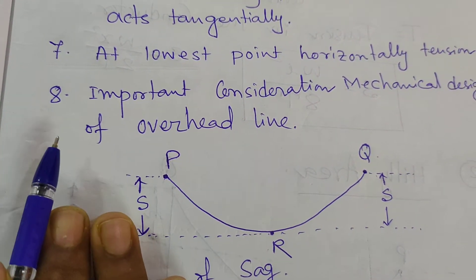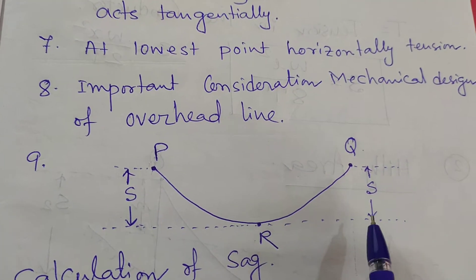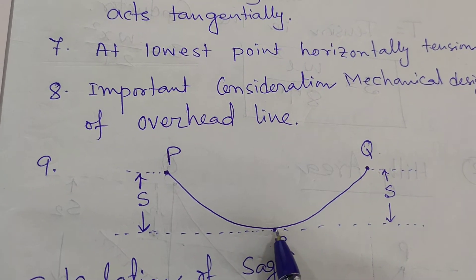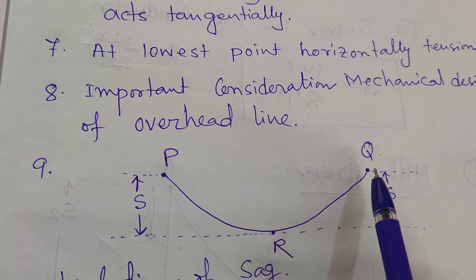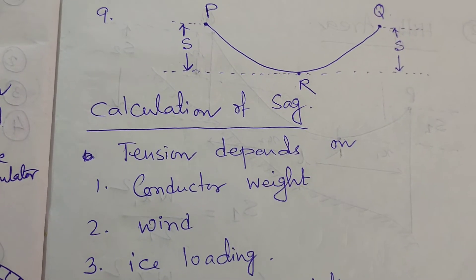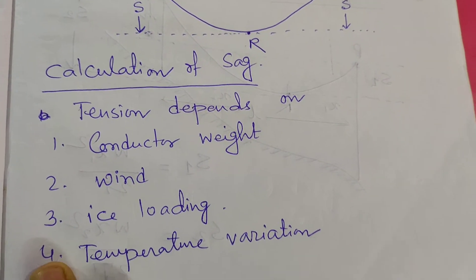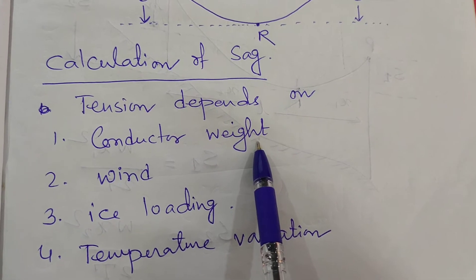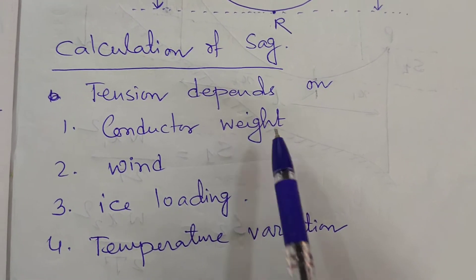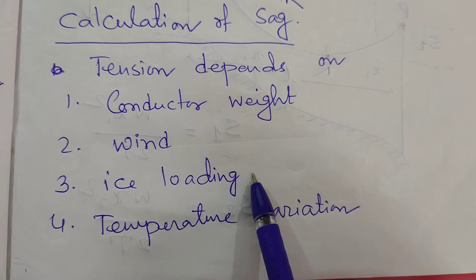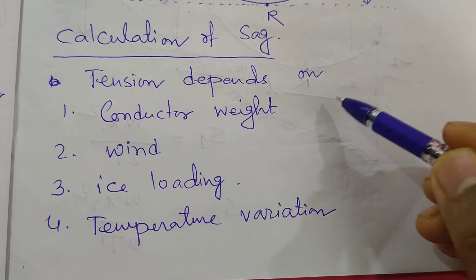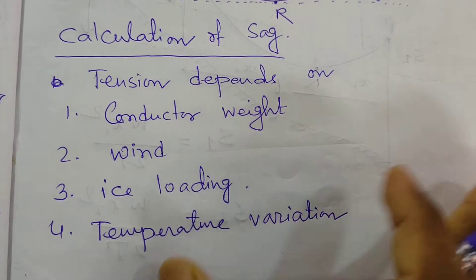This is also applicable for other cases. So this is also the SAG — the difference between the level of R and Q. The calculation of the SAG is very important. Tension depends on the conductor's weight. What is the conductor weight? It is the per unit weight of the conductor, the pressure of the wind, the ice loading, and the temperature variation. So the calculation of SAG and tension also depends on these factors.